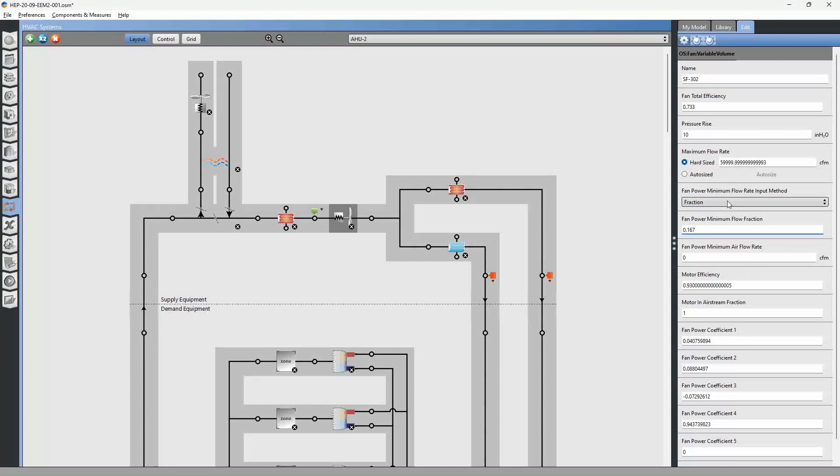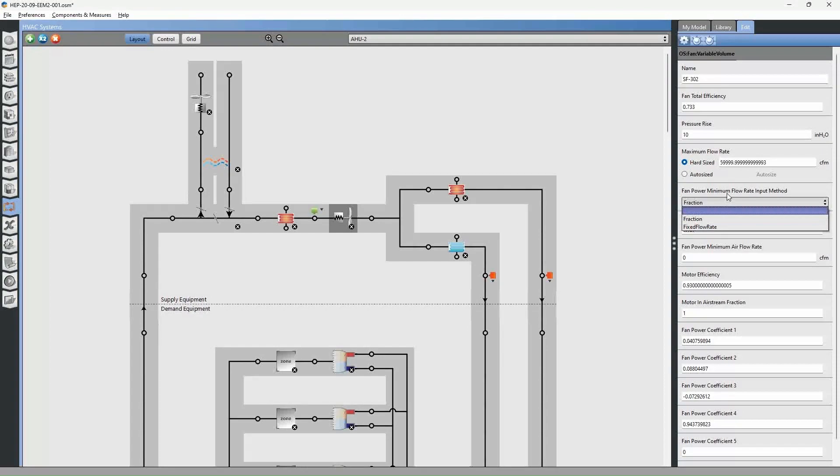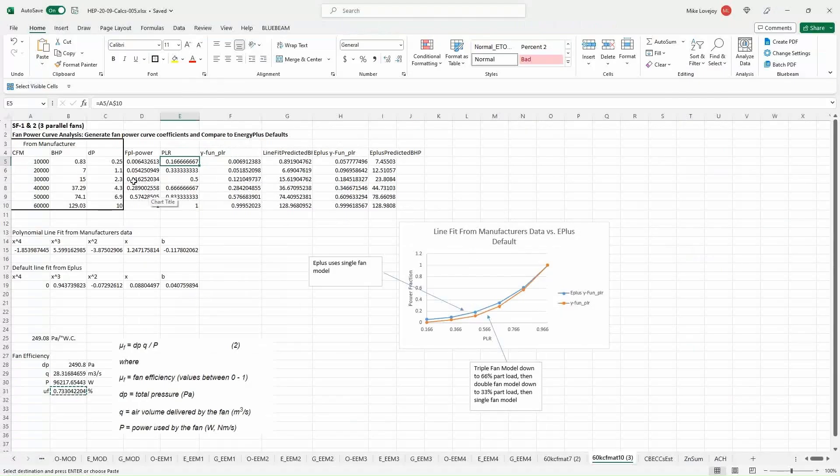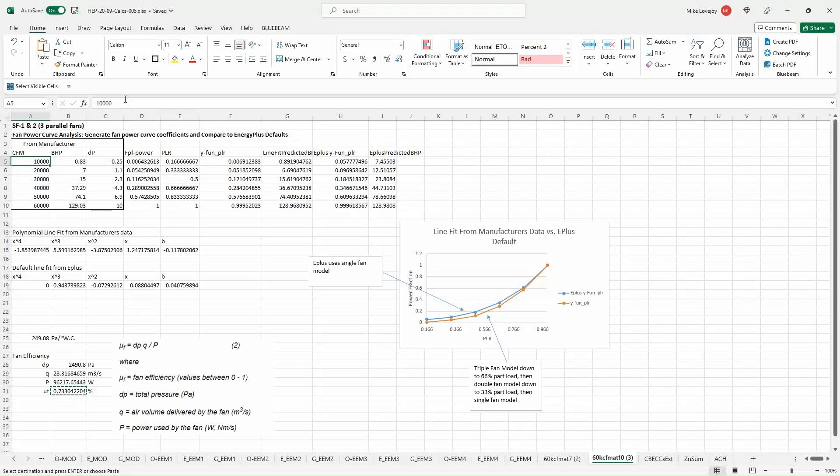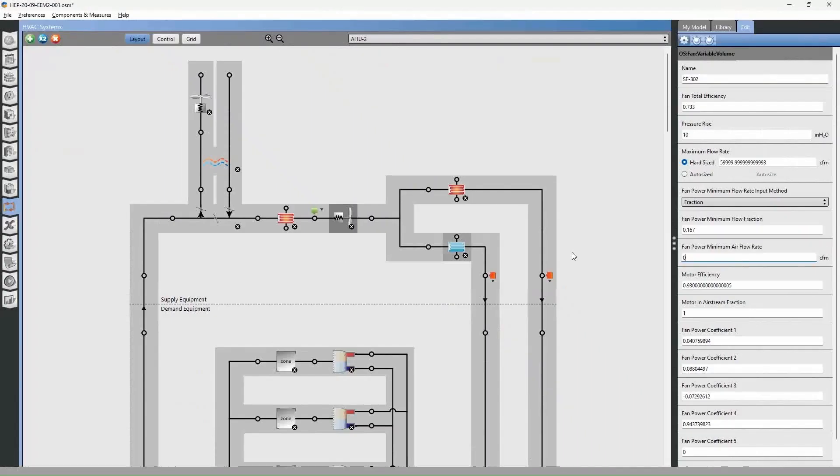And this is a fraction. So we're just going to leave this. This is a fraction. So it's referencing this. Alternatively, you could say that there's a fixed minimum flow rate. And in that instance, we would say our minimum flow rate is 10,000 CFM. So either way, you could specify it as a fraction or specify it as a flow rate.